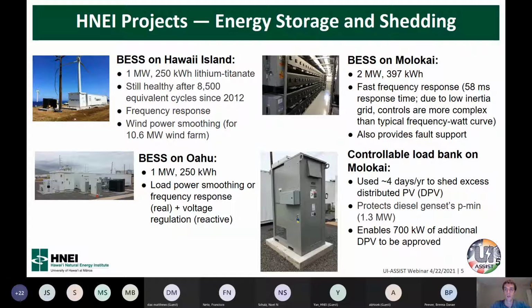Now on Molokai, some of the focus is on fast frequency response, because Molokai is a very small grid. It's about 5.9 megawatts peak, traditionally driven by diesel gensets. It also has around 2.5 megawatts of PV. Being that small of a grid with really low inertia, fast frequency response is a big issue.